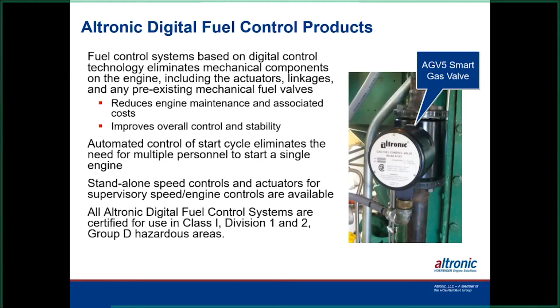Fuel control systems based on digital control technology eliminate mechanical components on the engine, like we talked about: the actuators, the linkage, and pre-existing mechanical fuel valves. It reduces maintenance costs and improves overall control and stability. It makes the engine start easier because it's got more control over a smaller amount of fuel, instead of running a big choke block valve that they've used in the past. And then they'd have to deal with the hydraulics of the governors. Being that it's all done with electronics internally, everything works much faster, and we can fine-tune it to a lot tighter, smoother control. So both systems are Class 1 Div 2 in Group D, so they can be run in a real hazardous environment.